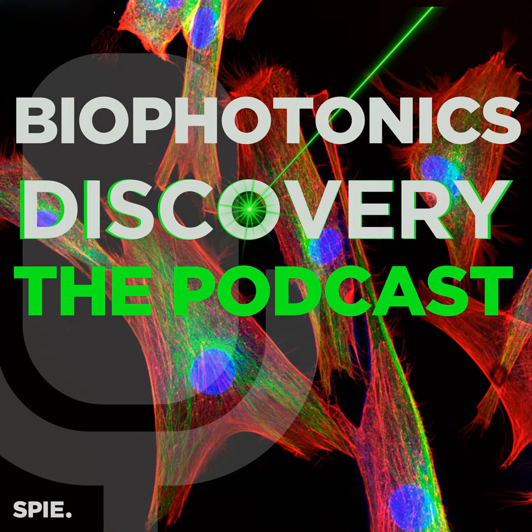And so I started working on this with some co-founders at Planoptica about a decade ago. And our original approach was we surveyed the existing ways to prescribe eyeglasses and measure what prescription you have, and learned that there's a technology called wavefront aberrometry that's very accurate, but unfortunately very expensive at the time and difficult to use and non-portable. So our mission became to try to translate this validated technology into a device that could be used in these low and middle resource settings to accurately provide eyeglasses just more efficiently.